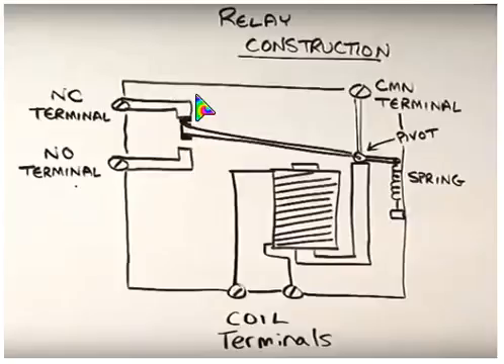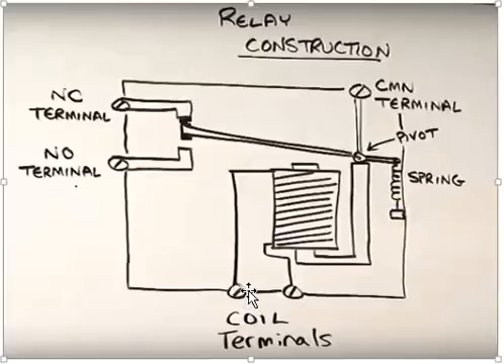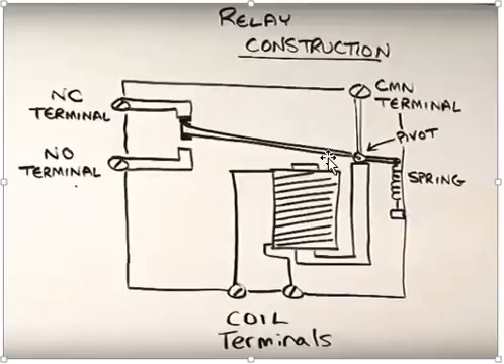Because of the spring, the armature is pulled upwards. The coil has two power supply terminals. If you give positive and negative voltage to these two terminals, the coil gets activated and becomes a magnet. The magnet attracts the armature and pulls it down, so the armature disconnects from the NC terminal and connects to the NO terminal.